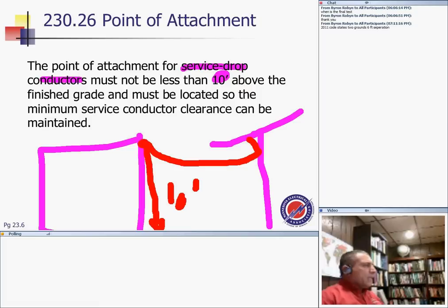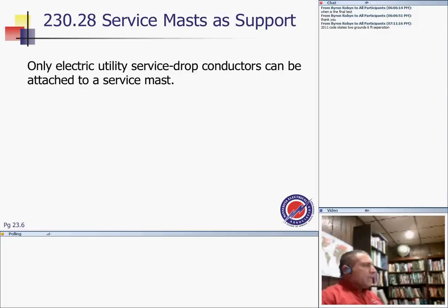Somebody else might go and put a deck here, right in this area, and then you are down to 5 feet. Down to 5 feet. It must be located so that the minimum service conductor clearances can be maintained, and don't ask me how you're going to prevent people from doing it. You can't prevent people from putting a deck in the backyard. Well, you're supposed to. Okay, any questions, my friends? Any questions?